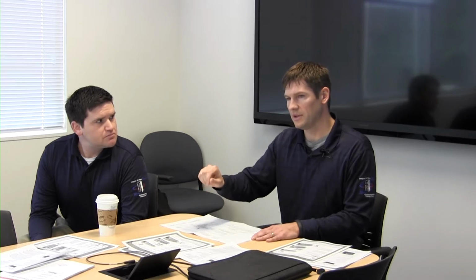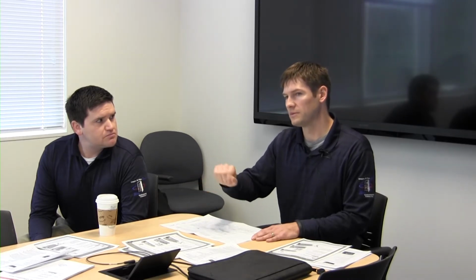It's controlled elsewhere. So for occupied mode, it just runs flat out, the fan? Yeah, constant volume. Okay, so all you're doing is modulating the water. Yep. And there is a dial inside, I believe, where you could pick medium, low, or high airflow. But there's no outside air introduced to it. And that's the same for the IT room split system. There's no outside air. The PTAC has a manual air damper, which you can move and set and fix. But the fan coil is relatively simple. I think it's got a stamped louvered grill on the top, which just directs the air one direction. It doesn't modulate. It's not adjustable.